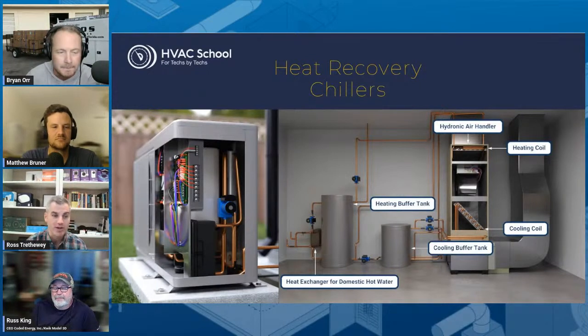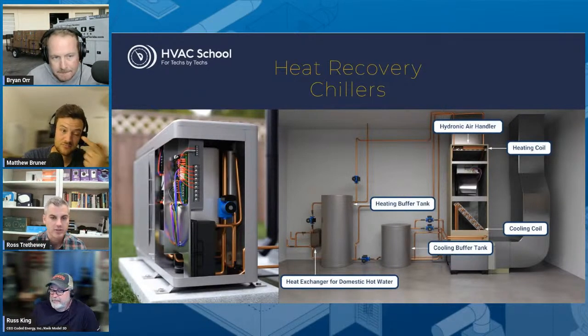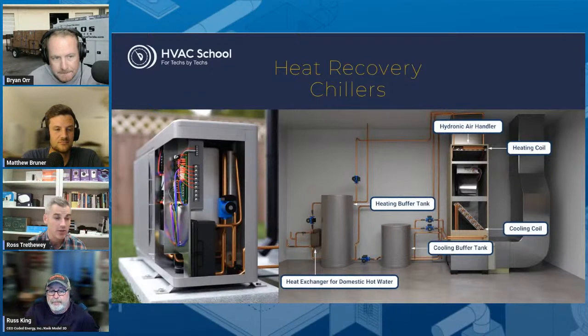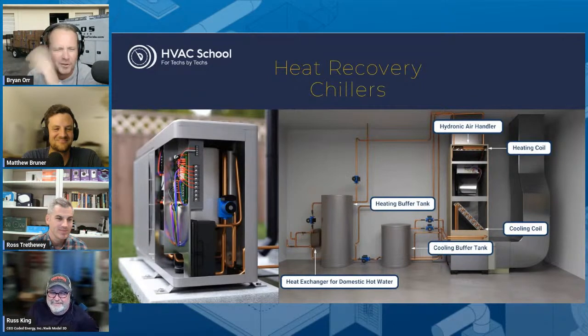Yeah, we did a segment on Future House for part of Ask This Old House. It was probably 6 or 7 years ago at this point, so it's definitely a little bit outdated. But it's 2 buried tanks in the ground, well insulated, one hot, one cold, running off an air-to-water heat pump, and being able to switch it back and forth between heating and cooling, doing that concept. So that's on YouTube and out there. But yeah, just to get a feel for what that installation might look like. Yeah, there's a show called This Old House, if anybody's heard of it. They do a few things now and again, and Ross is involved with that. So, go look them up. They've got a little YouTube channel out there.